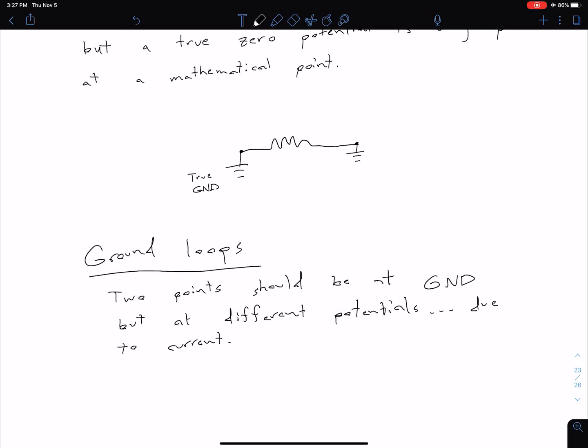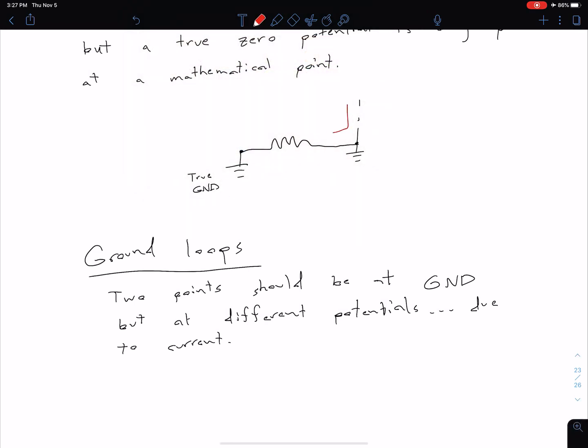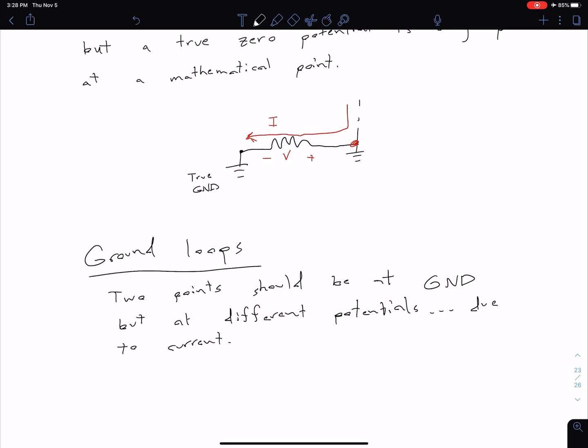This might be a small resistance value, but as our cabling lengths increase, that value can be larger and larger. So if we have some circuit causing current to flow through this resistance, we're going to have a voltage drop across it, which means that the point on the right is no longer going to be at ground. This is what we're talking about when we talk about ground loops.